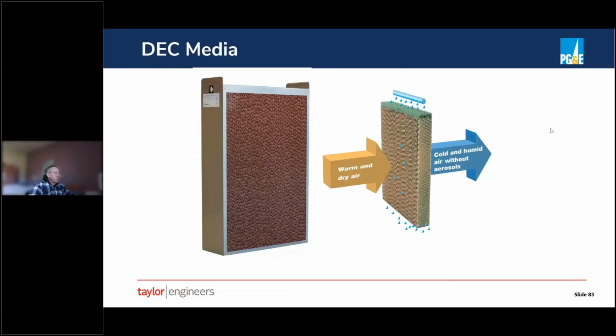So evap media is basically corrugated cardboard that you're dripping water over, so that dry air going into it comes out as cold and moist air coming out of it. And that temperature and humidity can be controlled by bypassing. We'll talk about a couple other options. One other nice feature of direct evap is that it provides an extra level of filtration. It's basically an air washer. And so not only is it cooling the air, but it's taking out some of the particulates and aerosols and things that may not have been caught by your filter. You're still going to have an outside air filter upstream of this, but you get an extra level of filtration with this air washer.